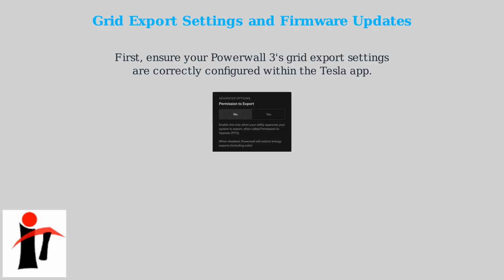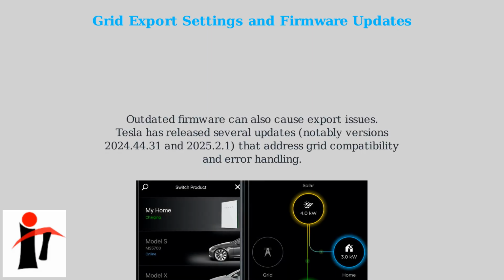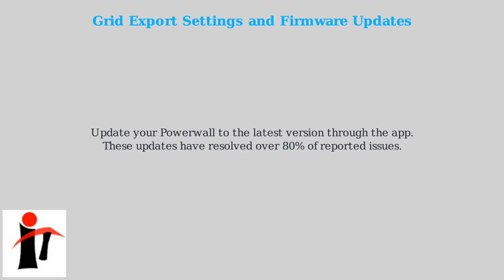First, ensure your Powerwall 3's grid export settings are correctly configured within the Tesla app. Outdated firmware can also cause export issues. Tesla has released several updates, notably versions 2024.44.31 and 2025.2.1, that address grid compatibility and error handling. Update your Powerwall to the latest version through the app. These updates have resolved over 80% of reported issues.